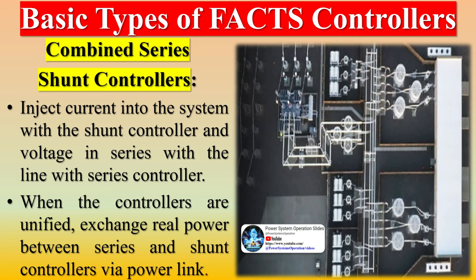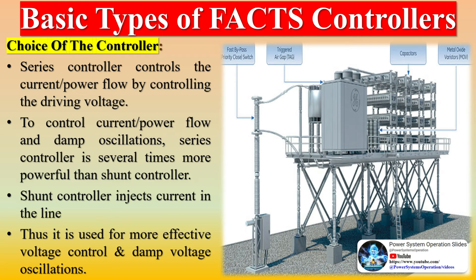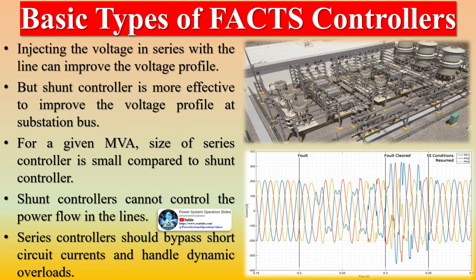In the choice of controller: a series controller controls the current and power flow by controlling the driving voltage. To control current, power flow, and damp oscillations, a series controller is several times more powerful than a shunt controller. A shunt controller injects current in the line and is used for more effective voltage control and damping voltage oscillations. Injecting voltage in series with the line can improve the voltage profile, but a shunt controller is more effective to improve the voltage profile at the substation bus. For a given MVA size, a series controller is small compared to a shunt controller.